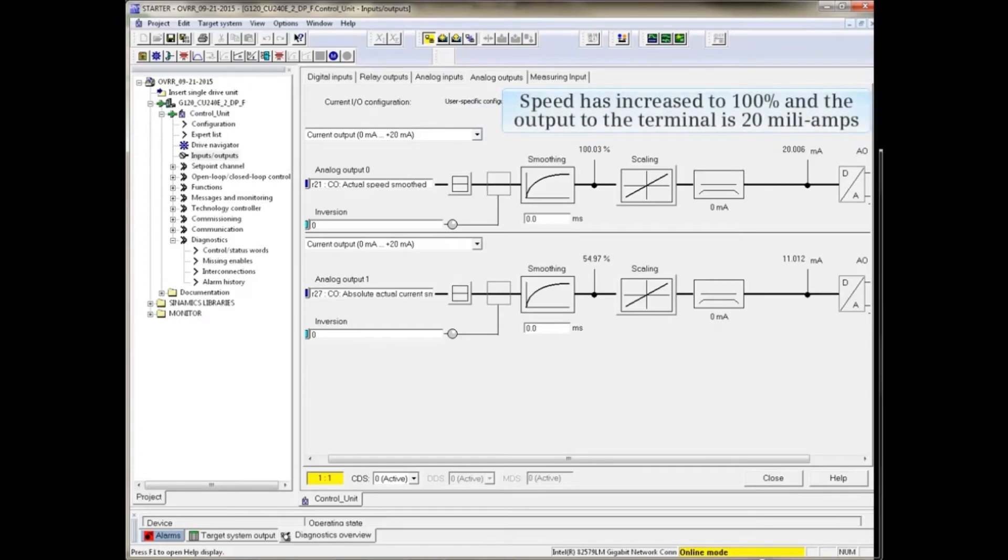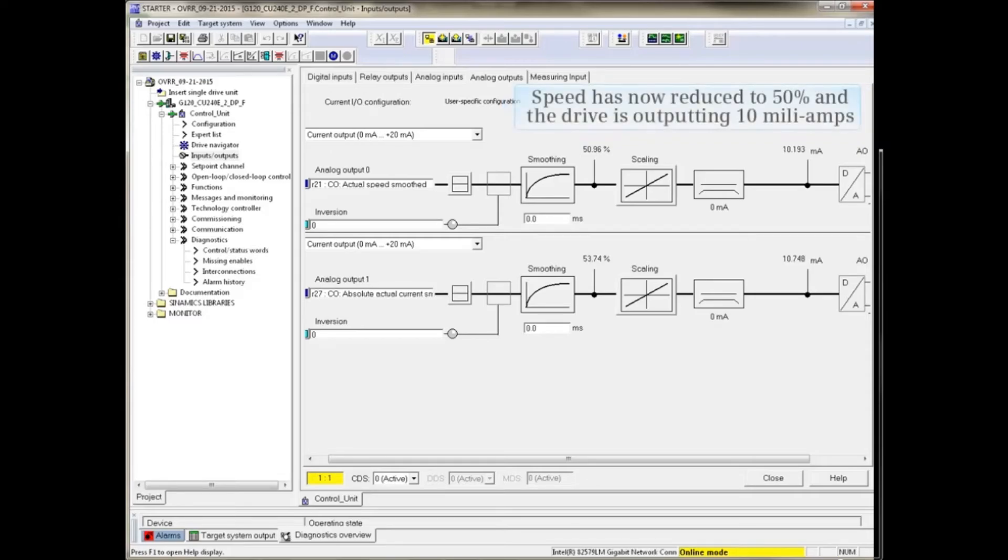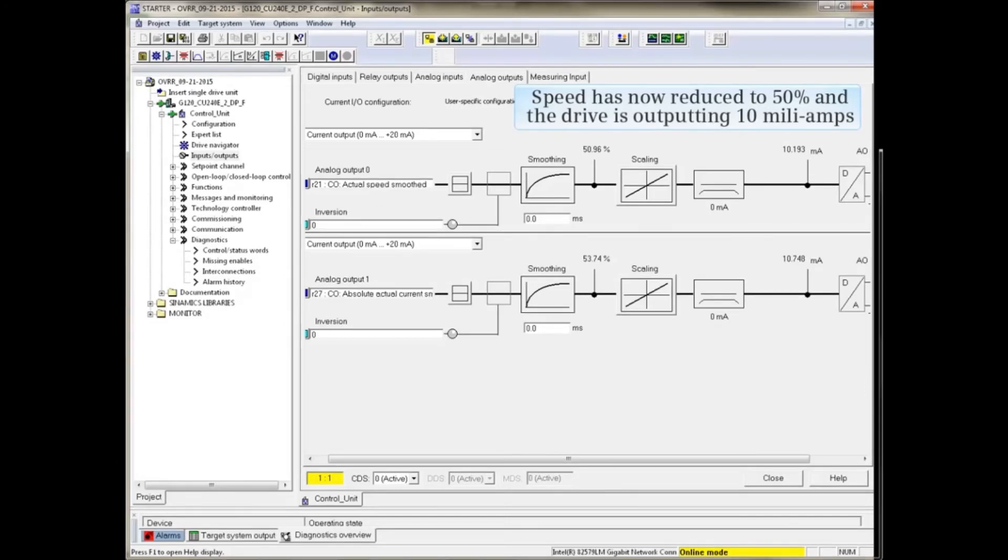Speed has increased to 100% and the output to the terminal is 20 milliamps. Speed has now been reduced to 50% and the drive is outputting 10 milliamps.